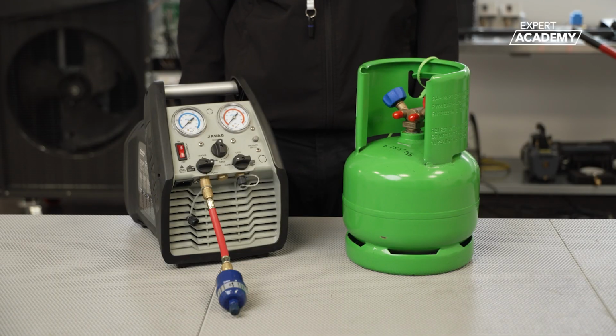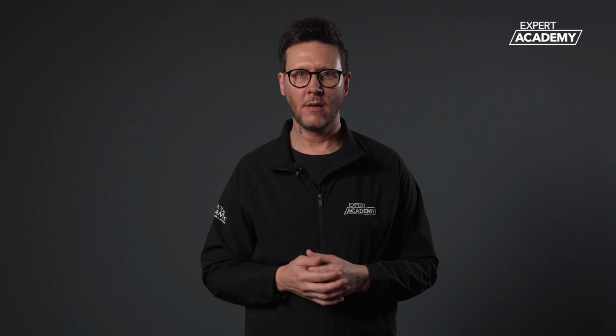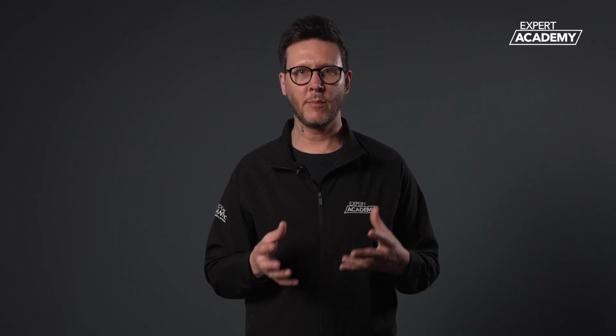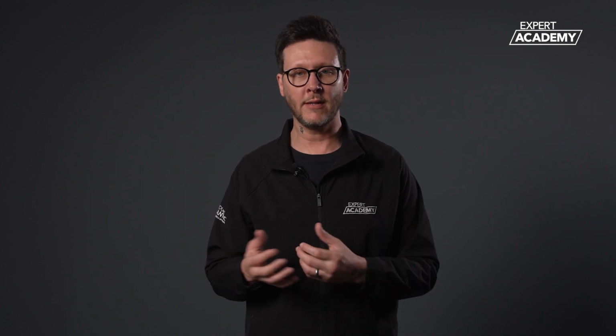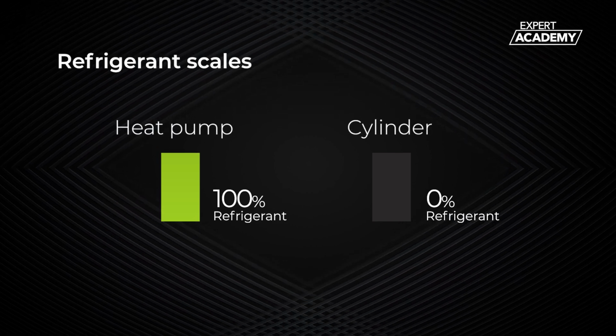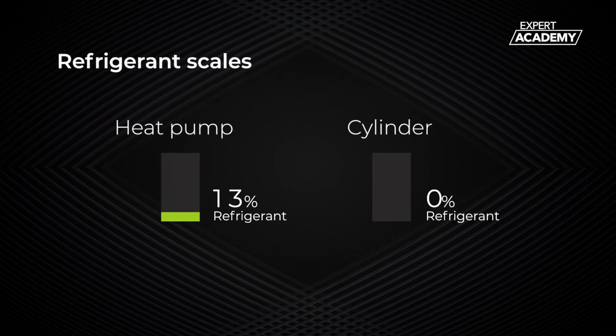The recovery machine helps us recover or extract the refrigerant from the heat pump. We need to do this before starting any work on the refrigerant circuit. For example, if we were going to remove the plate heat exchanger or condenser, one half of that circuit would be full of refrigerant. Therefore, we need to remove the refrigerant in a safe and controlled manner.